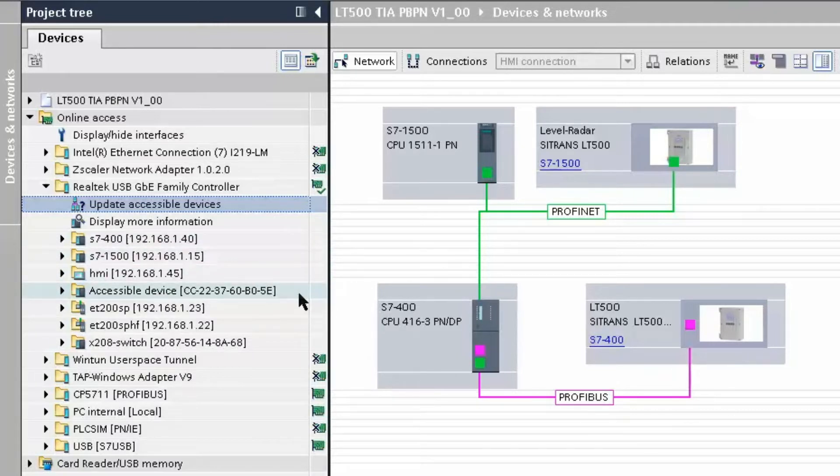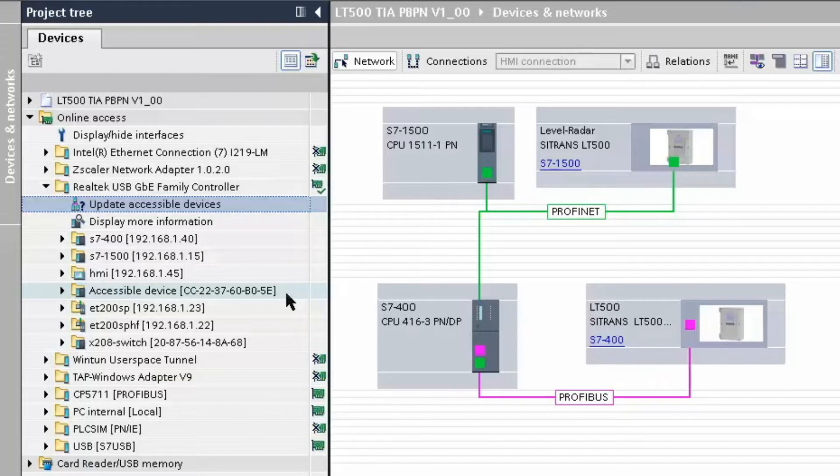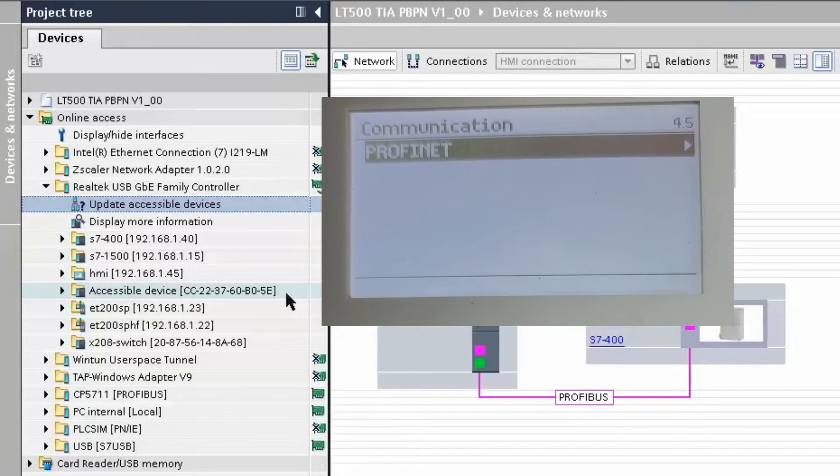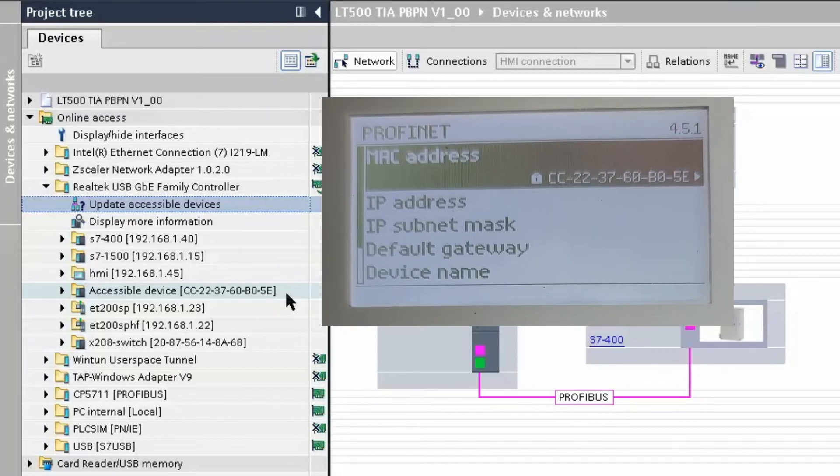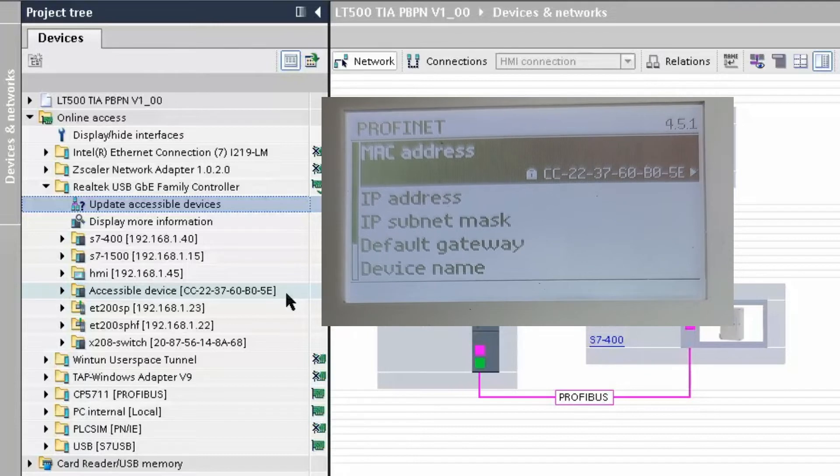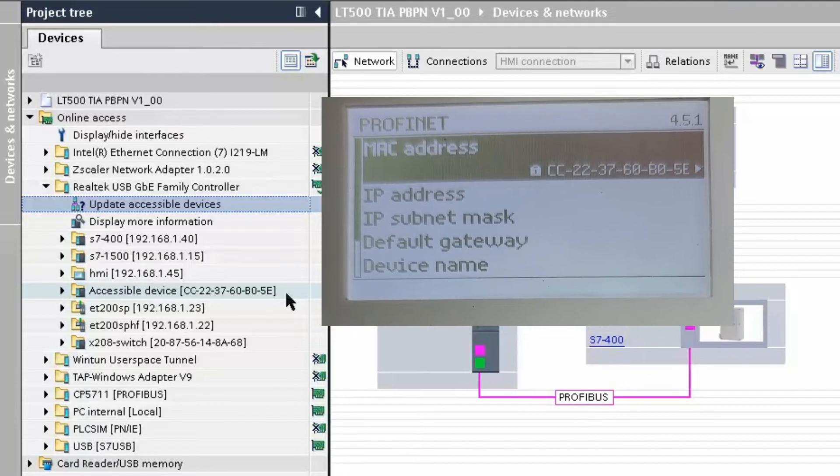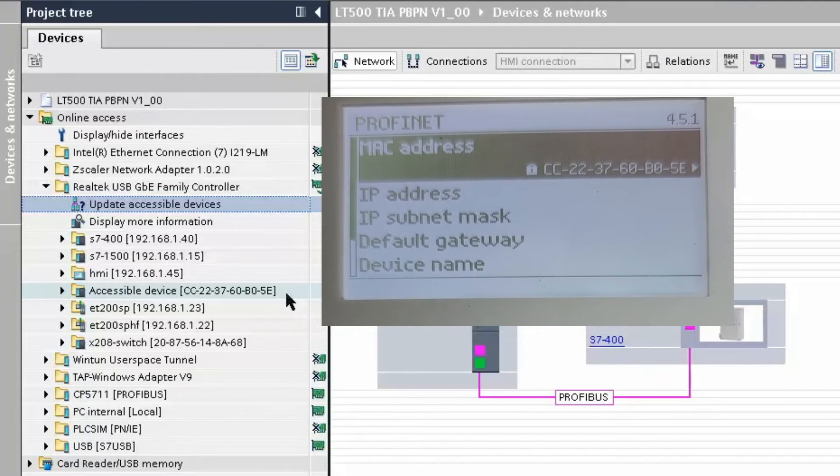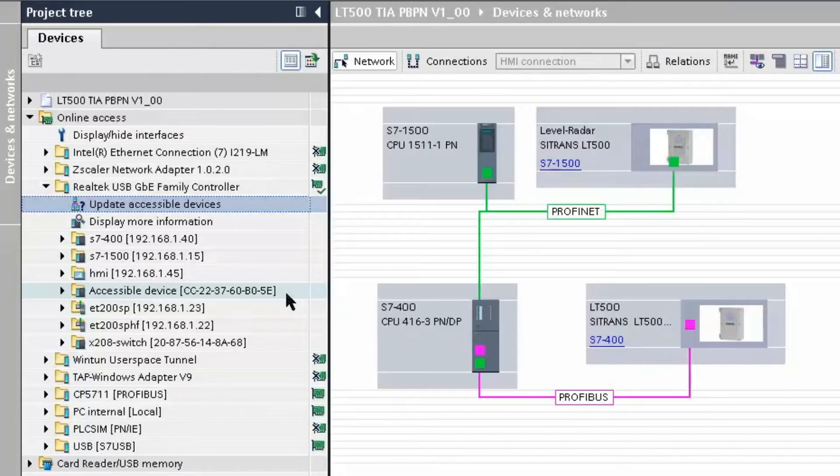However, there is a device here which does not have a name or an IP address. If we access the Sitrans LT500 through the local user interface and go to the Communication menu, we will see the MAC address of the LT500. So, the first thing we need to do is to assign a device name.